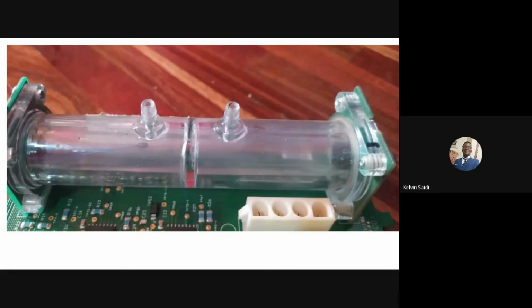The makeup of this ultrasonic sensor is that it has two transducers contained in a tube. This tube has an outlet and an inlet, which allows gas to flow from the product tank to the flow meters in an oxygen concentrator. The gas which goes in the inlet and goes to the outlet is mostly oxygen and nitrogen.